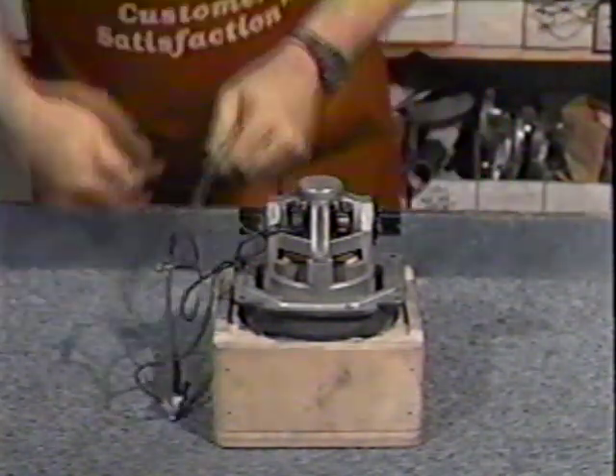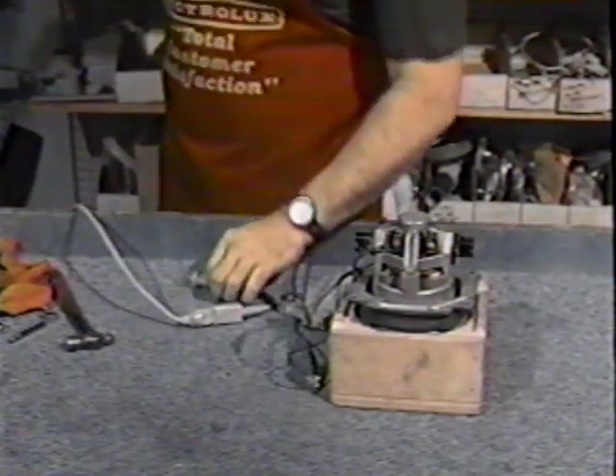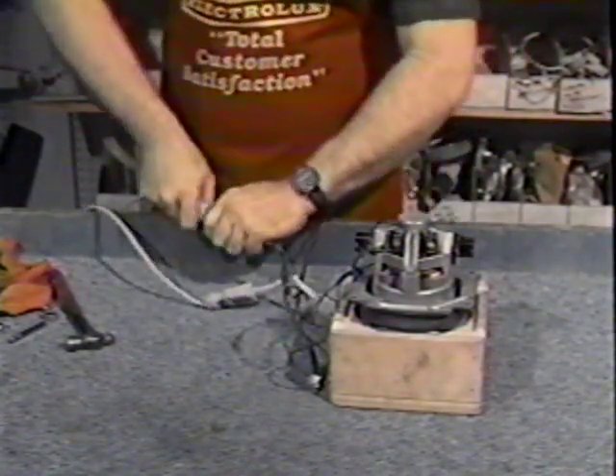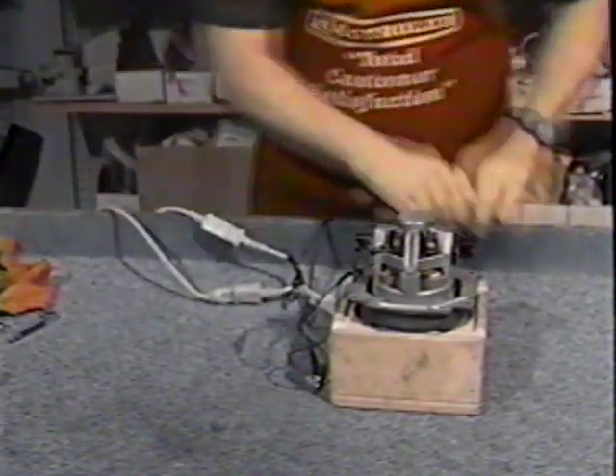If carbon brushes are replaced, the motor must be run in at 1/2 voltage for half an hour. To run the motor in, connect it to one side of the motor run-in cord. The other side is connected to a second motor or vacuum. Plug in the cord and both motors will run at 1/2 voltage.